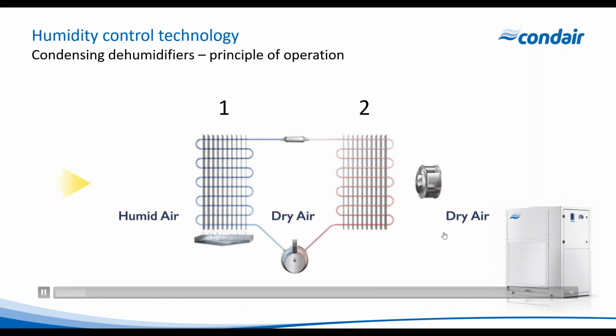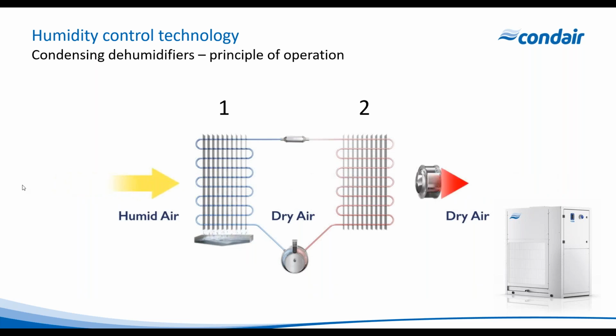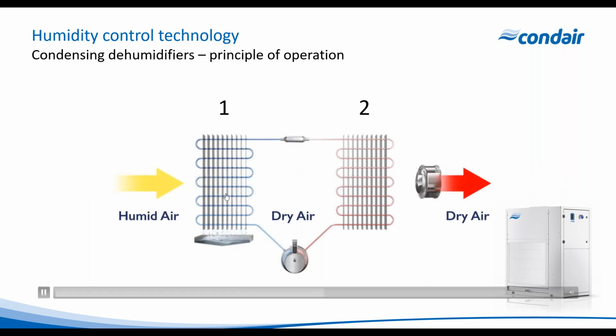Condensing dehumidifiers are usually used in the space, and they're a box that you typically put on the wall and attach a power and a drain to. But inside that box is effectively the same components as in your refrigerator or an air conditioning unit. So humid air enters the unit, and the first thing it comes across is a cold coil, an evaporator coil. It's called an evaporator coil because refrigerant is evaporating inside that coil. So it's lowering the surface temperature of that coil to a point below the dew point of air. And as soon as we go past the dew point of air, we know condensation is going to occur.